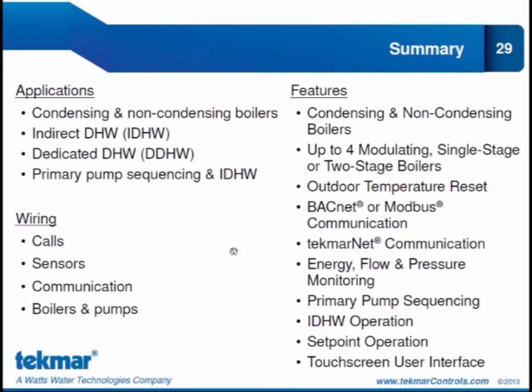We looked at BACnet or Modbus communication to a building automation system, and we did say that we'll cover that more in an upcoming webinar, and that more information can also be found in the BAS manual. tekmarNet communication, which you're familiar with, but we did look at how we have 4 boiler buses so that we can connect to up to 96 tekmarNet devices.